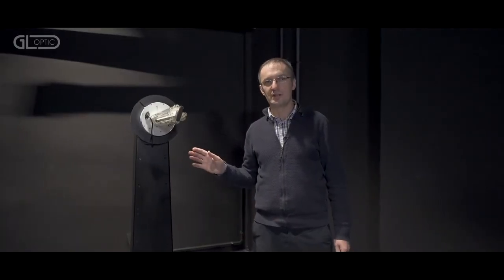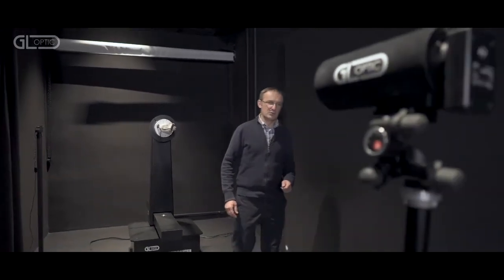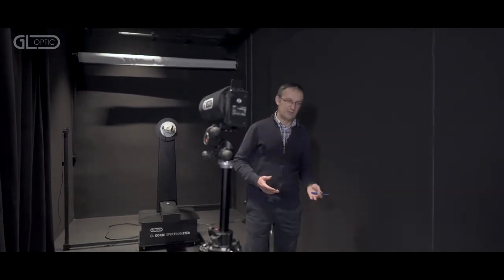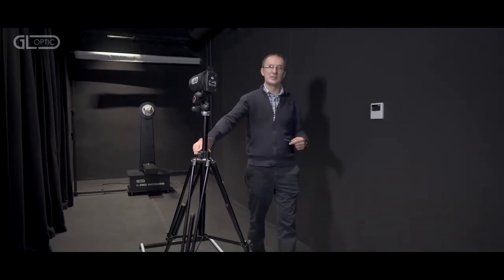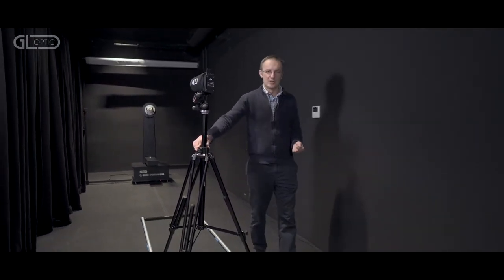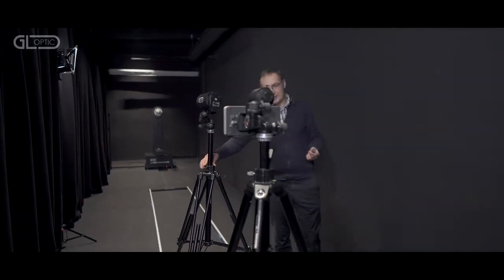With the unit installed and positioned on the goniometer, now it's time to set up the right detector and a measuring distance, which will allow a proper measurement and treatment of the device as a point UV source. For that reason, we set the correct distance of either a radiometer or a spectroradiometer, which of course needs to be sensitive in the range of the UVC radiation where we want to measure and characterize the device.